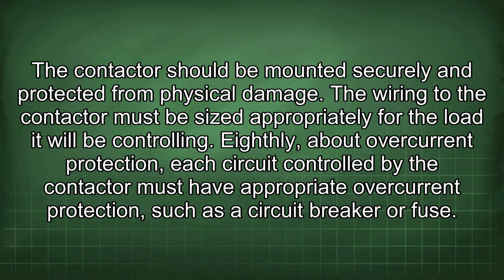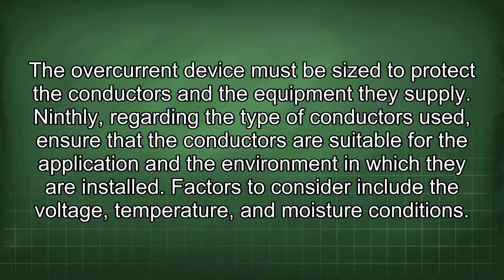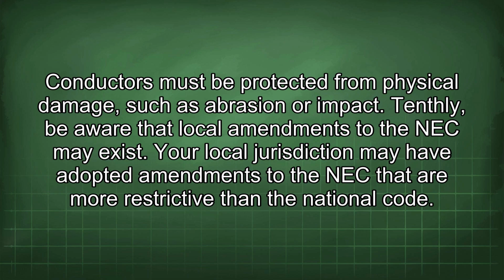Eighthly, about overcurrent protection, each circuit controlled by the contactor must have appropriate overcurrent protection, such as a circuit breaker or fuse. The overcurrent device must be sized to protect the conductors and the equipment they supply. Ninthly, regarding the type of conductors used, ensure that the conductors are suitable for the application and the environment in which they are installed. Factors to consider include the voltage, temperature, and moisture conditions. Conductors must be protected from physical damage, such as abrasion or impact.